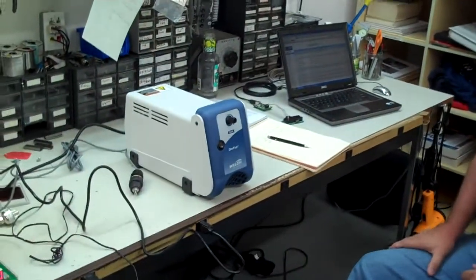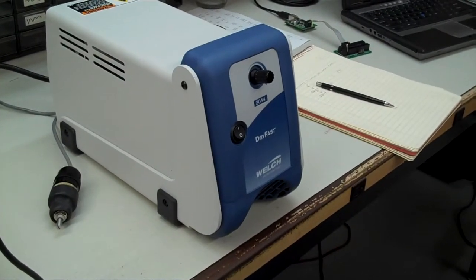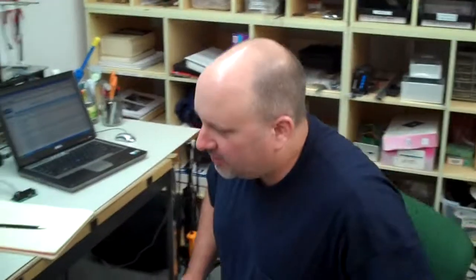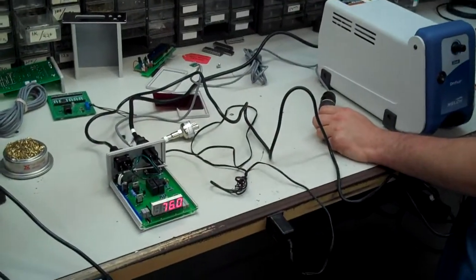We'll outfit one of our model 200 wide range vacuum gauges with one control at minimum, two for an extra control, test it, and send it back to you ready working. Here is a Digivac solution to controlling your pump. Customer requested 25 torr pump turn on.